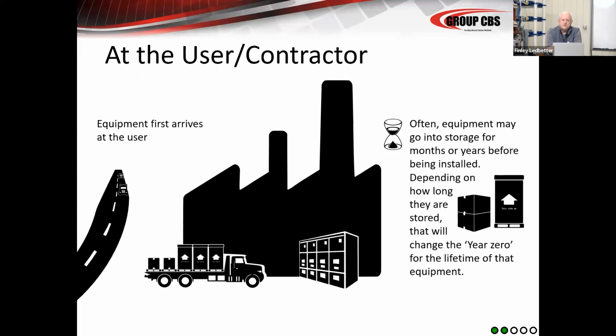I've seen it frozen in warehouses with high humidity. I've seen all sorts of horror stories. So hopefully, let's say that it's stored properly with heat on it and it's not stored very long. I've seen this equipment in storage for many years before it's installed. I've also seen it come directly to the plant and go directly onto the pad off of the truck from the manufacturer and be installed and energized in a few days.